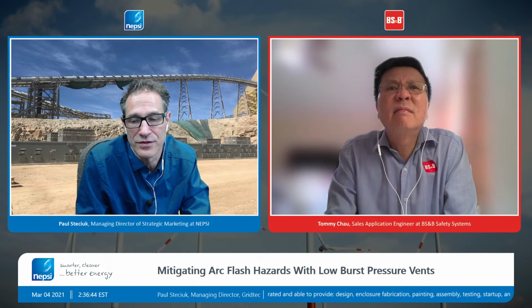So on a typical basis, metal-enclosed systems are not specified as arc resistant. It's those customers that say, hey, we want arc resistance, we want more protection for our employees, what can you do? And this is how we handle that request. We put in these low burst vents. So it's not something that we add. They do have some costs associated with it, and they need to be planned.